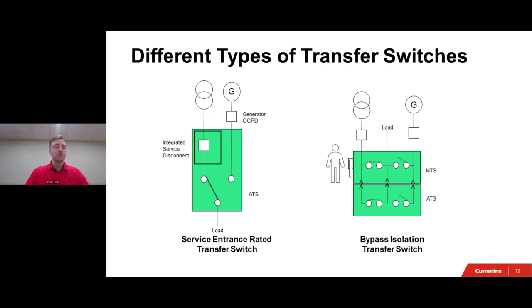And to cover those non-service entrance rated automatic transfer switches, they are any automatic transfer switch that is not capable of doing any of the items mentioned above. And for those that are visual learners, lastly is that bypass transfer switch, which is off to the right there with, once again, the little human standing next to it.